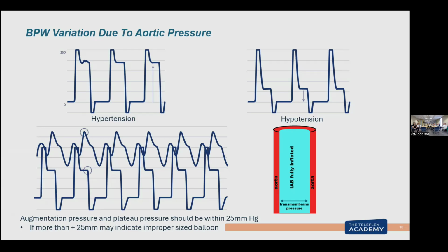Because we know the pressure that the pump is using to deliver that volume, we can compare what's going on with the aorta. When the balloon is inflated, your augmentation pressure on the arterial line is the pressure against the balloon at the time the balloon is inflated. And we can measure this pressure because this is calibrated. There's a constant relationship between the plateau and the augmentation. The plateau pressure should be within 20 to 25 millimeters, plus or minus, of my augmentation. So this plateau pressure could be 25 millimeters higher to 25 millimeters lower. What that tells me, if I've got it in that range, is one, the balloon's in good position, probably hitting the second to third intercostal space on my anterior chest x-ray, and we're getting about 85 to 90% occlusion.